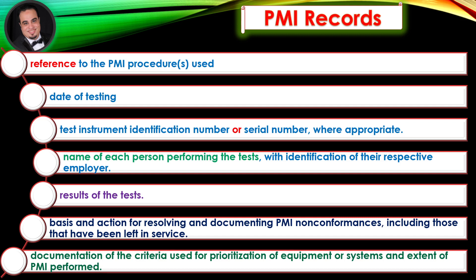PMI records should also include results of the tests, basis and action for resolving and documenting PMI nonconformances including those that have been left in service, and documentation of the criteria used for prioritization of equipment or systems and extent of PMI performed.